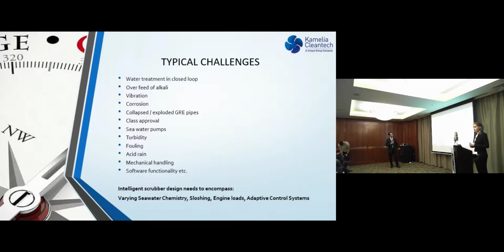And then one thing with commissioning, or in operation, is collapsed or exploded GRE pipes. This is again an inexperienced crew ramping up the VFDs too fast, or you don't have enough wall thickness on the pipes, or you're not taking care of the banging of the seawater in the pipes somehow by engineering solutions. So class approval has also been difficult in the beginning, but now class is getting more on board, so I don't see really issues with that unless your system is not compliant.